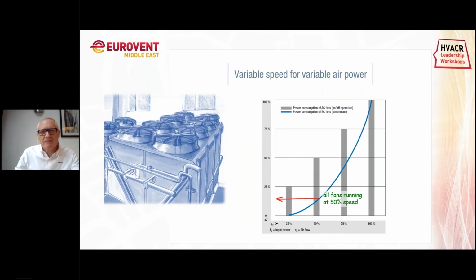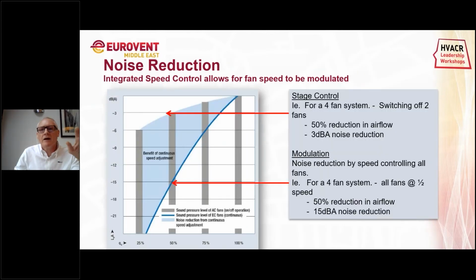There are some other benefits from EC fans as well, and one of them is noise reduction. I think we heard Mikhail talk about that earlier. If you take a 4-fan system and reduce the fan power by 50%, say in the colder months in January or in the evenings when the temperature drops, you may want the fans to modulate to a lower speed and optimize the head pressure in the refrigeration system. If you reduce it by 50% just by turning 2 of the fans off, you're going to get a 50% reduction in airflow, and that results in about a 3 dBA noise reduction.